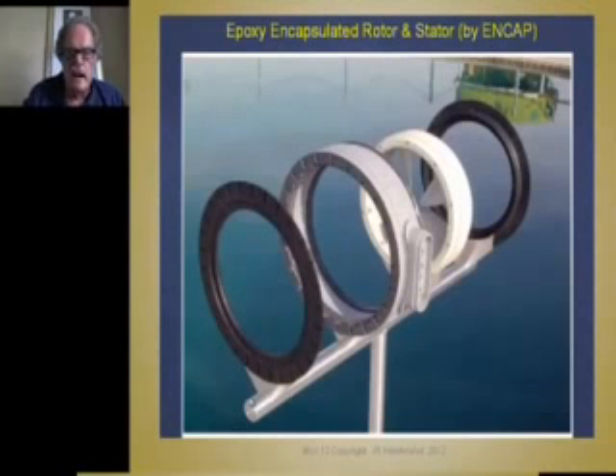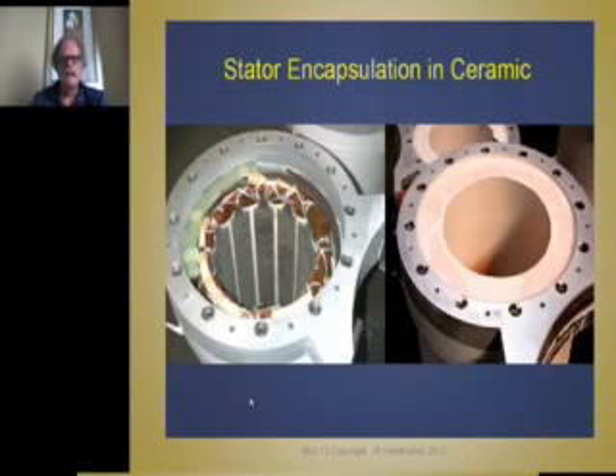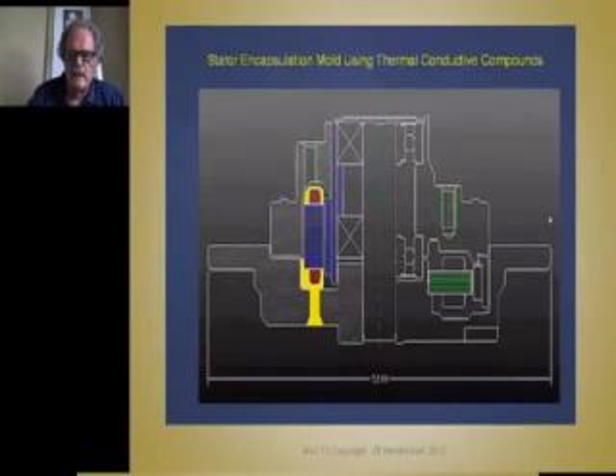But this provides very good thermal conductivity from the conductors through this material to the seawater to cool it. And here's an example of a stator that's been encapsulated with this ceramic material. You can see there's the aluminum housing with the core fitted in there with all the windings and lead wires in place, and then it's completely encapsulated with this ceramic thermoconductive material.